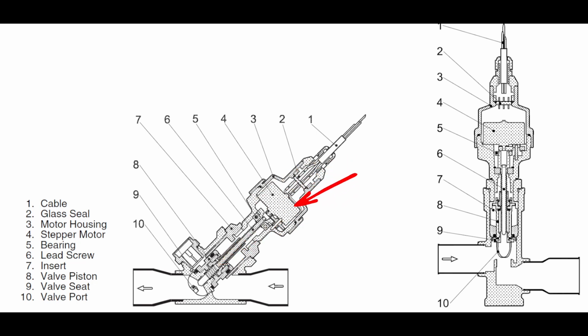These valves are designed off of a timed cycle, very similar to an actuator. A lot of, say, floating point actuators are based off of time. They could be either a 60-second, a 30-second, or a 90-second actuator, right? And so we know that in that time, that actuator takes 90 seconds to go from 0 degrees of rotation to 90 degrees of rotation. That's very normal actuator terminology. Well, EXVs have that exact same process. You have a 30-second valve, a 60-second valve, something along those lines.